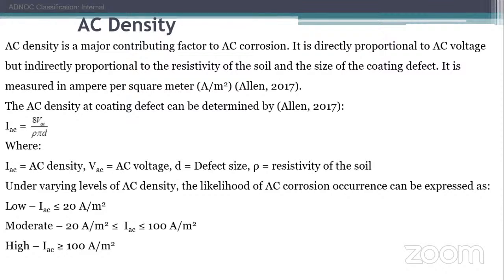So for AC density to happen, the high voltage transmission line must introduce current; there must be AC voltage inside the line. Secondly, you have to consider the resistivity of the soil. If the resistivity of the soil is high, the current can't come out from the pipeline, it will resist this flow, and AC corrosion will be controlled. Also, if the diameter is big enough, the AC density will be low.